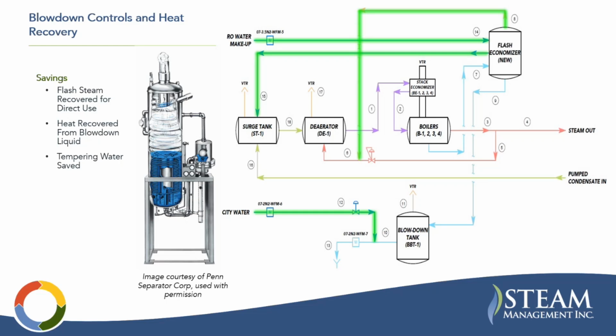And then last but not least, typically this blowdown is going to come into the bottom blowdown tank, flash off, and this tank's going to sit around 212 plus degrees. Most facilities have sewer temperature limits where the drain of that has to be tempered down to 140 degrees to not damage their drainage system or sewer system. So there is typically a tempering water valve here that is a significant amount of water used just to cool this down. With these heat recovery systems, this exit temperature is often going to be down to 90, 100, 110 degrees, but well below that sewer limit. And so you're mitigating this tempering water requirement.